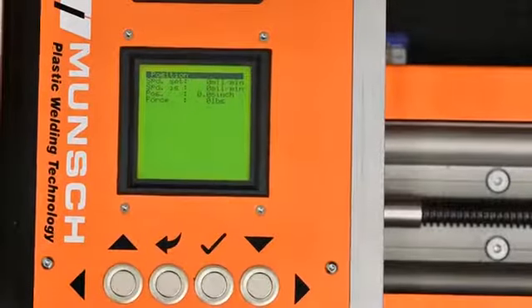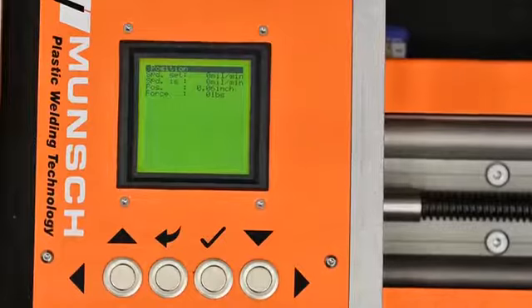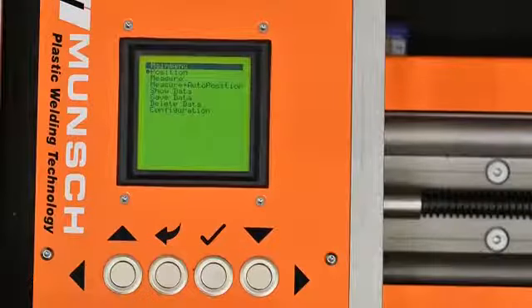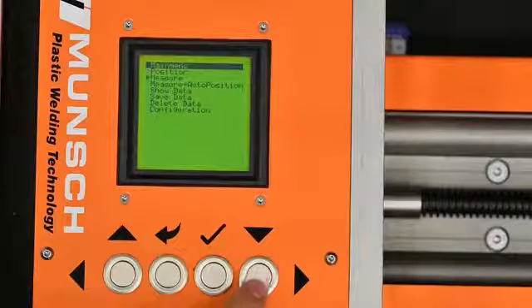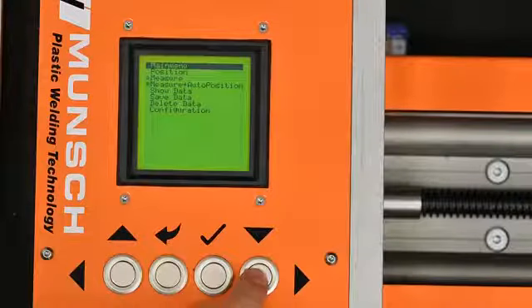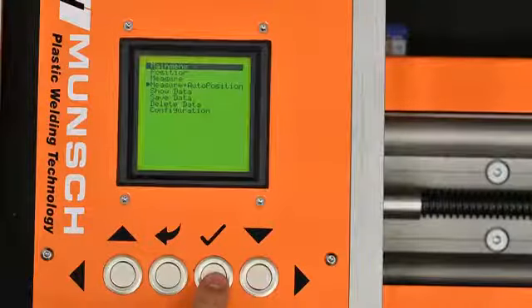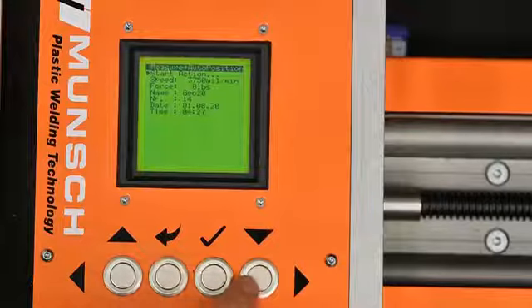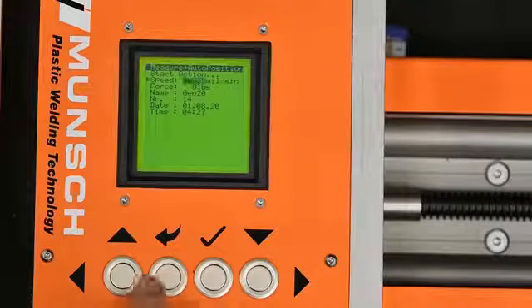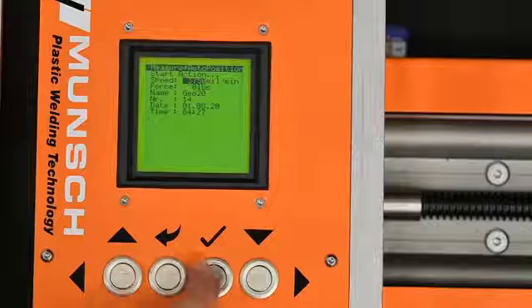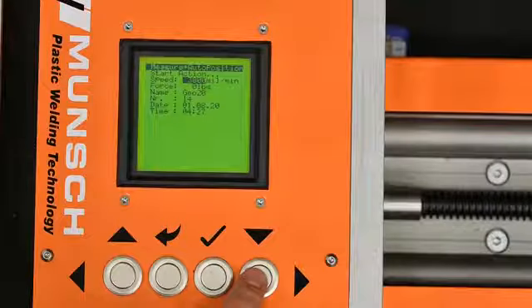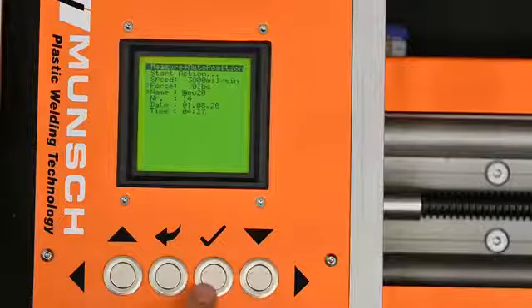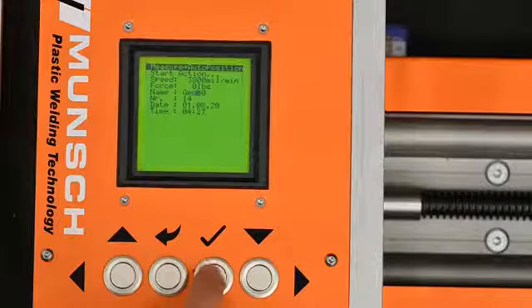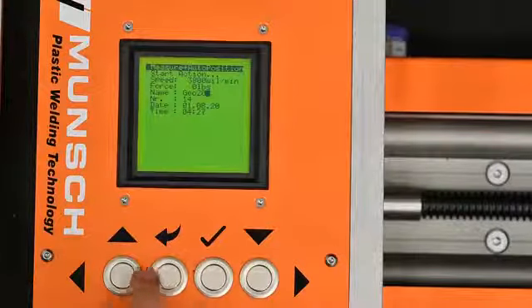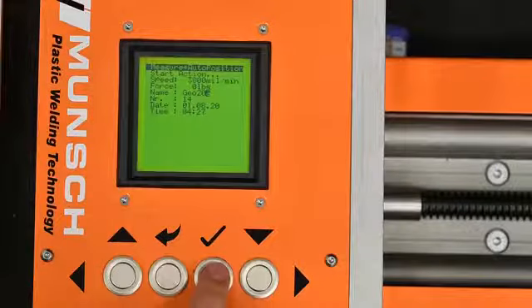The machine has two possibilities for starting the tensile test. The easiest way is if you select the option Measure and Auto Position. In the menus Measure and Auto Position and in the menu Measure you can set the testing speed, set the force to 0 in case it shows a small force, and set a name, for example site name or name of the welder. The machine automatically creates the test number, but you can override it in case it is necessary.